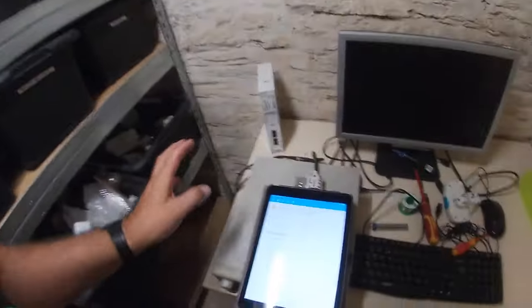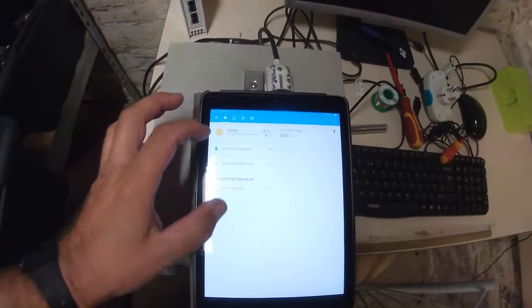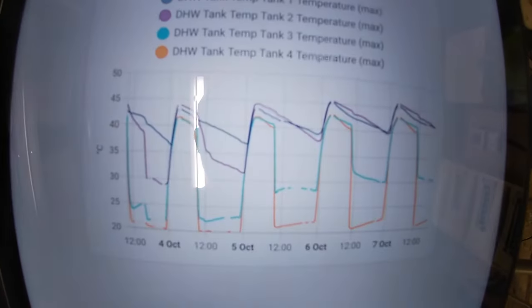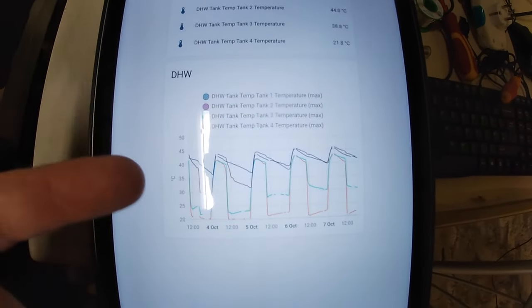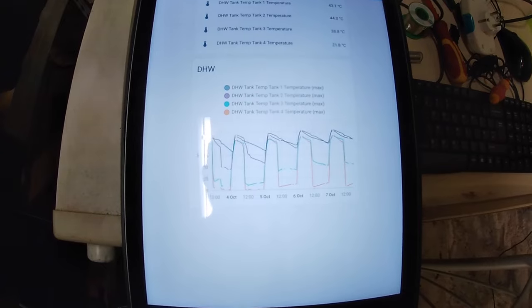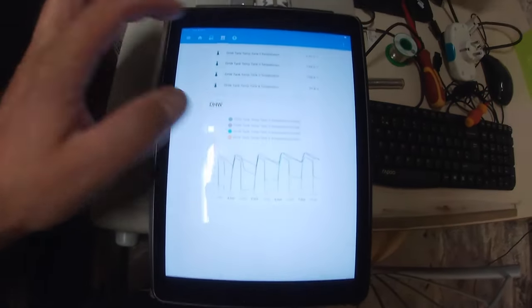So I'll just show you how that manifests on here. This is an overview. Currently the top of the tank is 40 to 43 degrees, and the house is using about 660 watts. If you want more information you can go to the heating side of things. There you go — current temperatures at the tank. This graph is the last five days. You can see the temperatures at different levels — very quickly the bottom goes down to about 20 degrees, but the top does maintain the temperature. I've had four or five people staying in at one time, that's why the maximum temperature never reaches the top. But now it's back to 45, which is what it's set at.